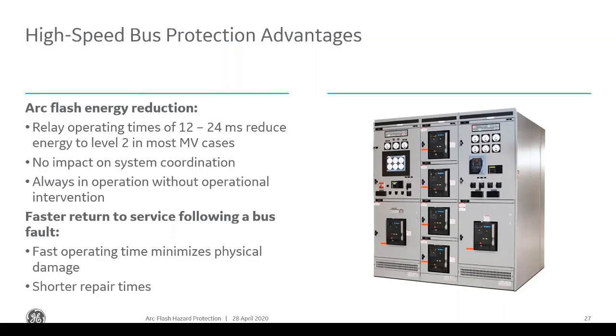So what are the advantages of having high-speed bus protection? Obviously, for arc flash energy, it reduces the trip time: most relays today are at a cycle or less for bus differential. So it can reduce any arc flash incident to about level 2, if not level 1, because depending on the breaker you have, we're talking about no more than a cycle for the relay, maybe 4 cycles for the breaker, could be 5 cycles, or if you have a 2 cycle breaker, then it could be 3 cycles. So it's very fast, and you can reduce your rating to either level 1 or level 2 very easily.